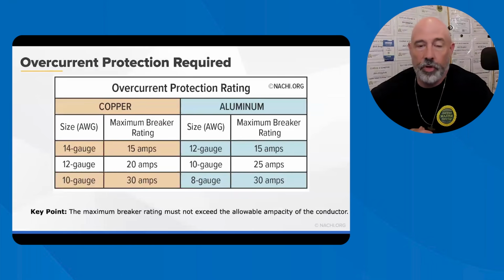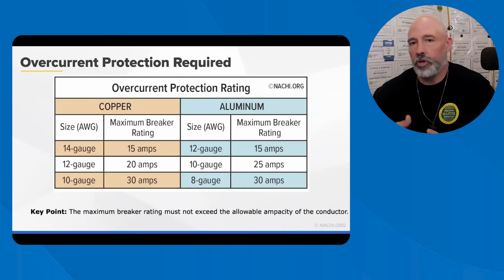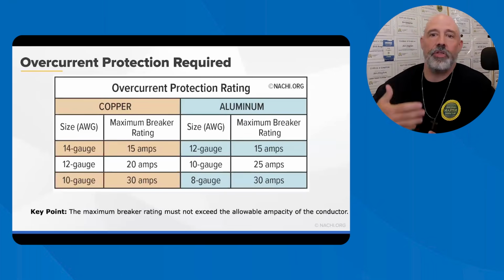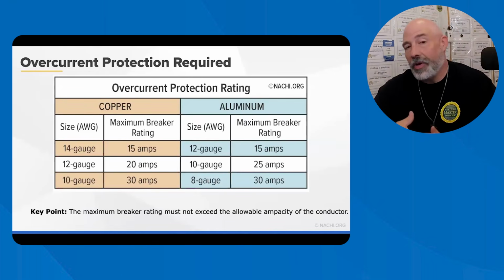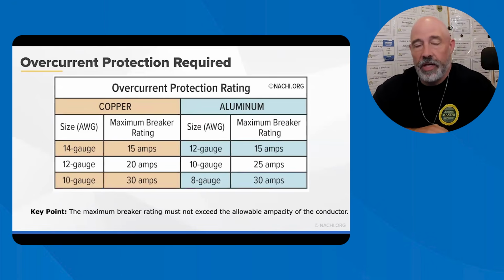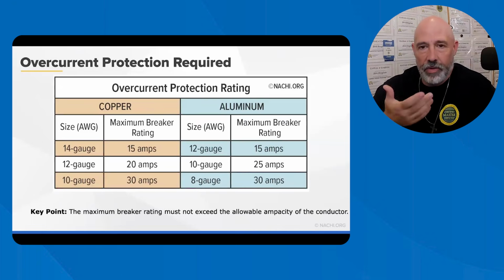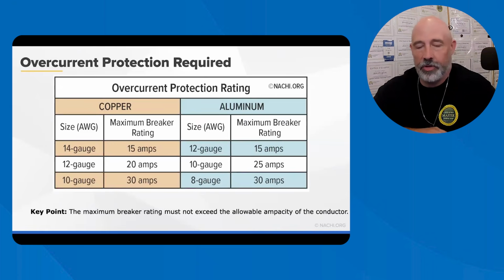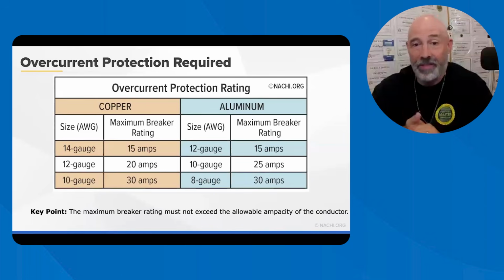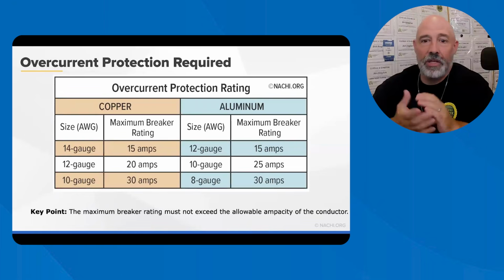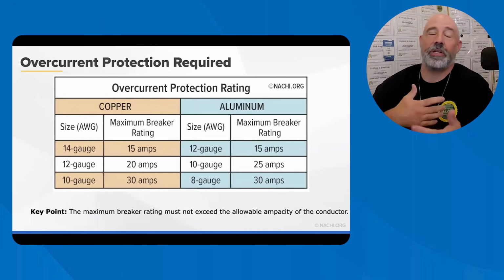When you're looking at the overcurrent protection that's required, all ungrounded conductors must be protected by an overcurrent device, such as a circuit breaker or a fuse. Their job is to prevent conductors from carrying more current than they were designed to handle. I had an inspection once at a house, and they said their fuse was blowing all the time. I asked, what do you have running on there? He said, I've got my microwave on there, and every time I plug in the toaster, it pops. Well, it's on the same circuit. It's going to pop. That's too much for that wire, and too much for the 15 amps.